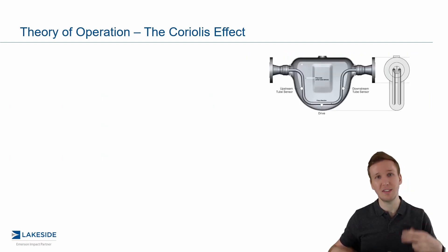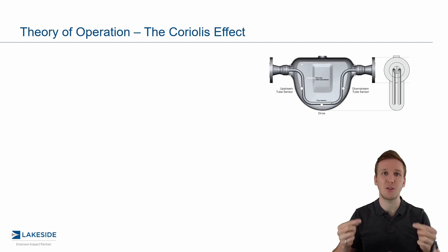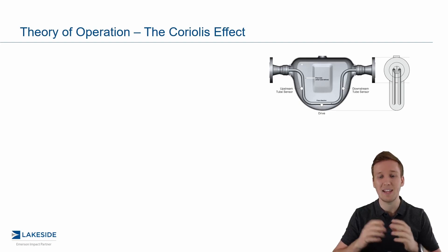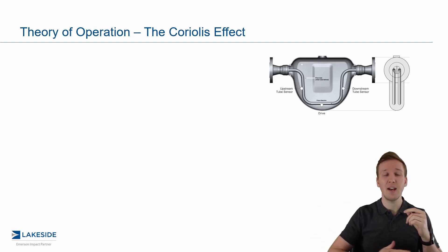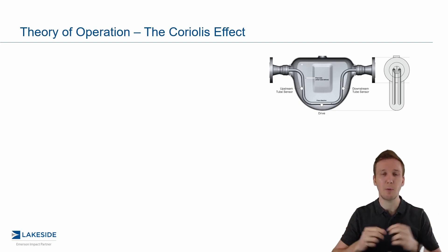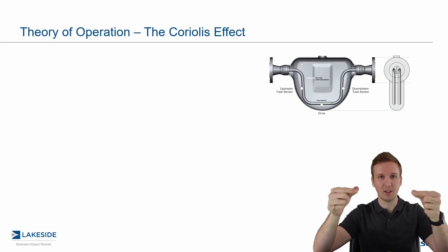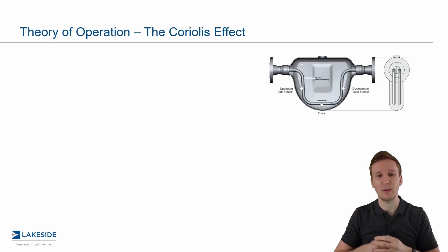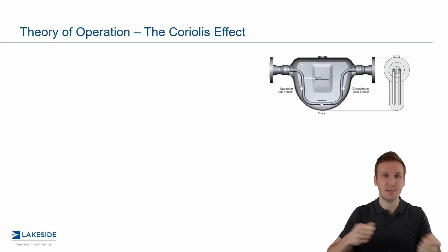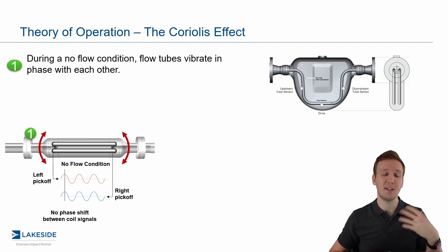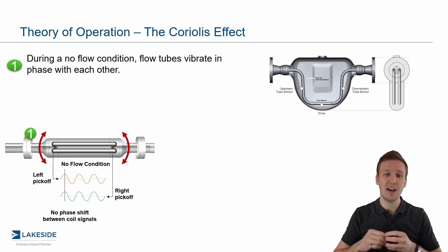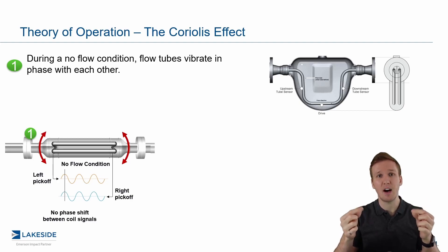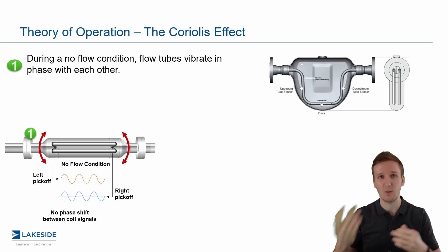The difference is we use two tubes instead of one garden hose, so that we can measure a delta between the left side and the right side. Flow travels down and then back up and out in a U shape — that's on purpose. The two tubes are fixed at a point near the top so they can free-hang. In the center we have a drive coil which drives them to a consistent frequency — much more accurate than shaking manually. When there is no flow, the left and right sides are in sync, and the pick-offs tap together at the same time. There is no phase shift difference between the left and right pick-off.